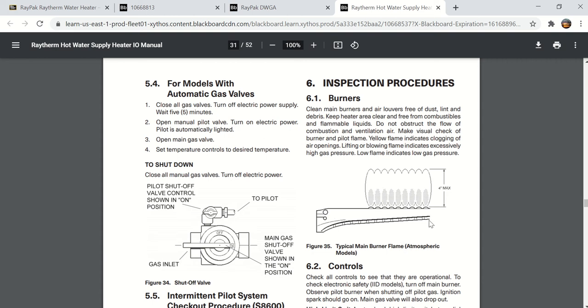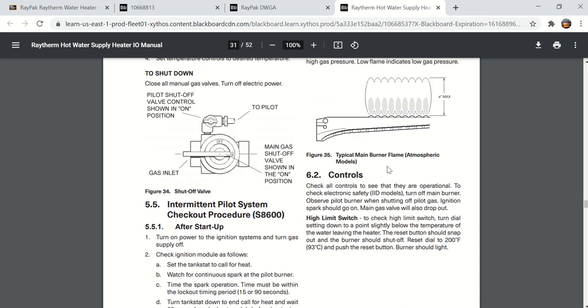So it has what's called ribbon burners. And here they're showing that the ribbon burners should not have more than a 4-inch tall flame maximum. But this is pretty typical for a smaller light commercial residential type boiler. And cleaning those ribbon burners is an annual maintenance kind of thing. You typically would want to do that in the fall. Pull the burners out, take a wire brush, take a shop vac or compressed air, and get them cleaned out.